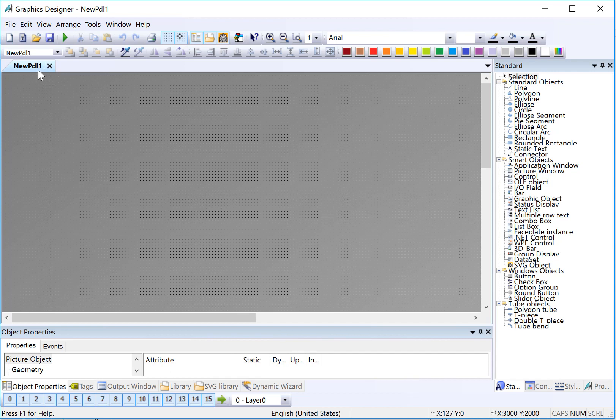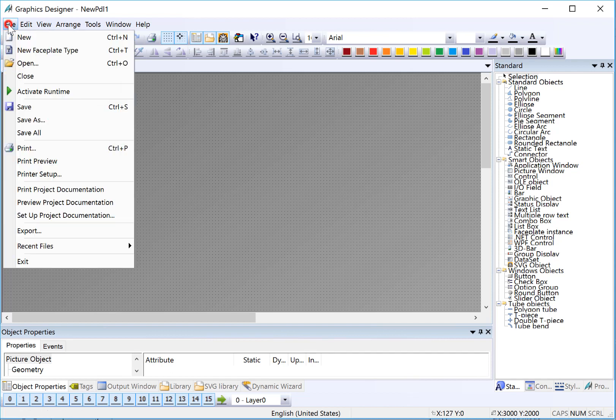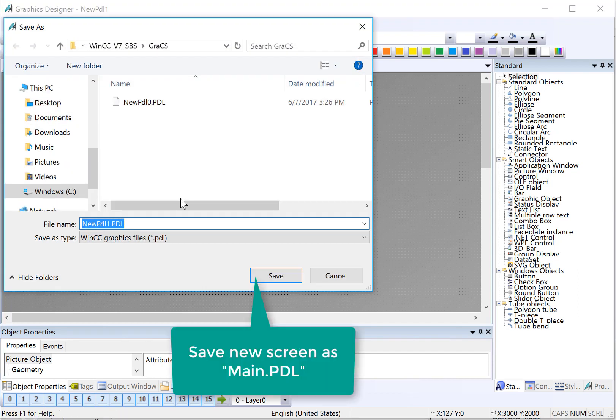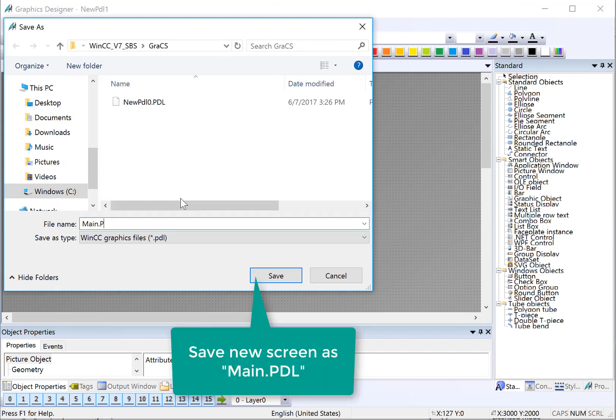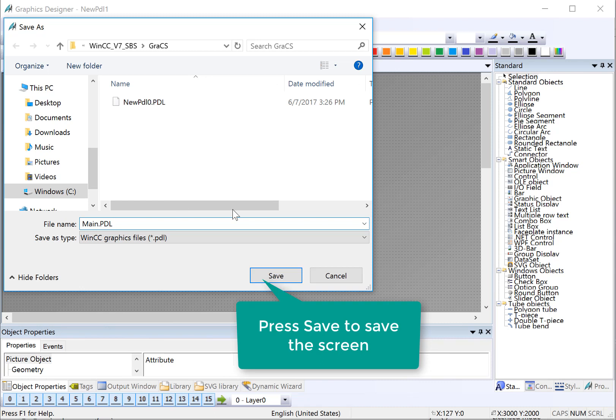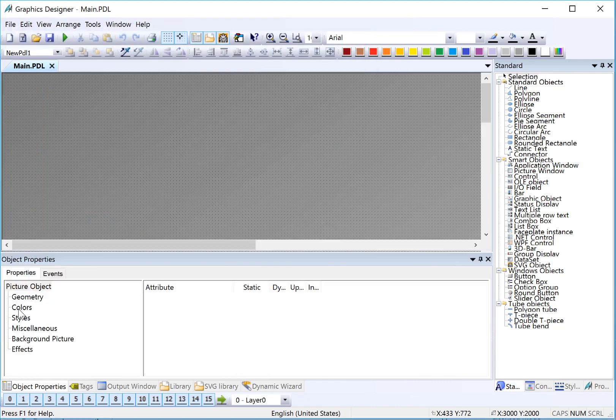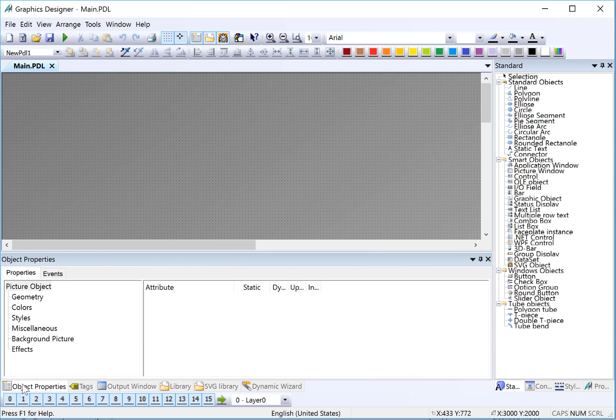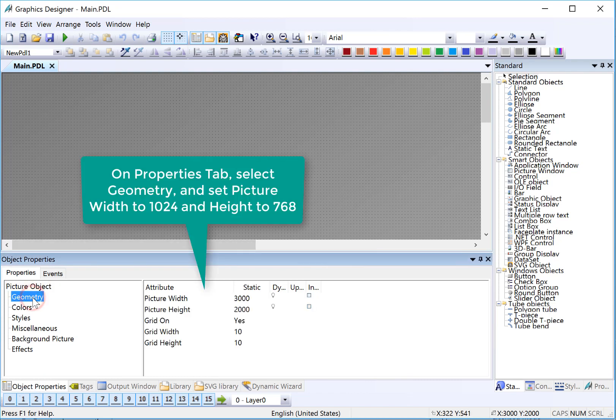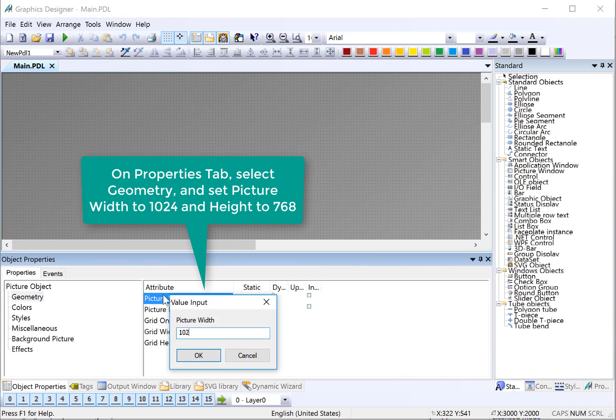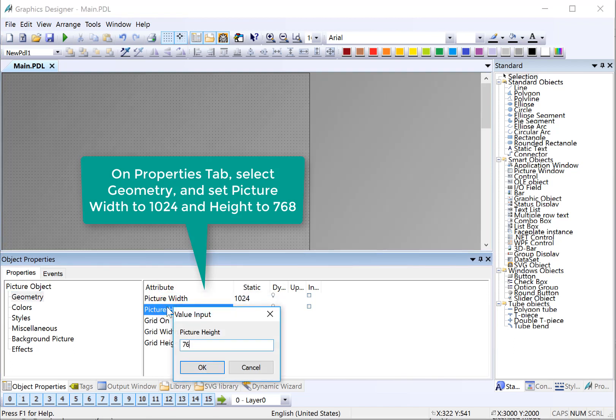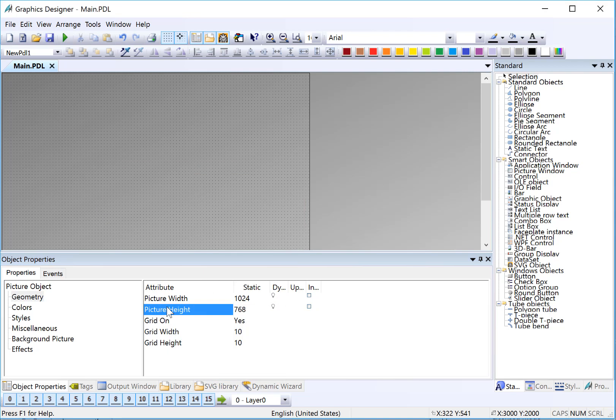The first thing I want to do is save this to the proper name and resolution. So I'll do file, save as, and we're going to call this main.pdl. Next, I'm going to set the screen resolution. My properties dialog is docked below, so I can just pull it up to have more access to it. I'll go to geometry, and I'll set my picture width to 1024, and my height to 768. And of course, this is going to depend on what target hardware you're going to run these screens on. It may be a smaller panel, or it may be a large screen.